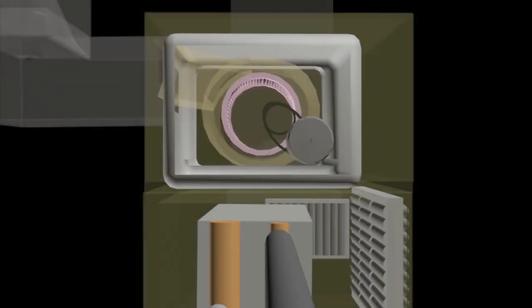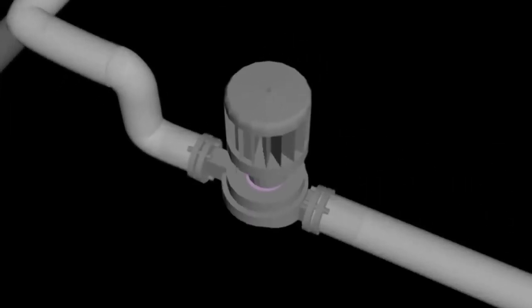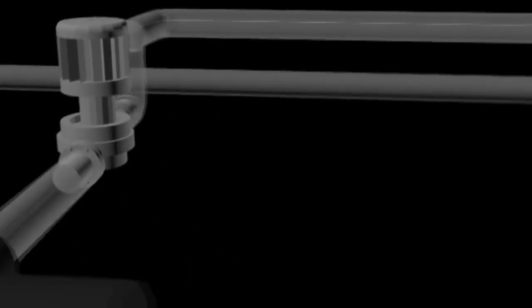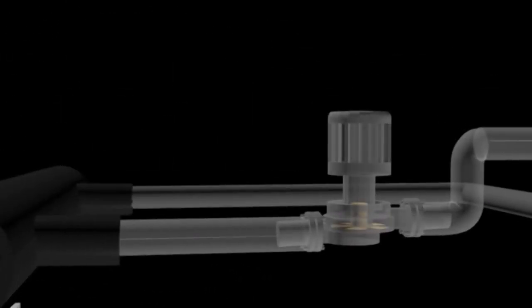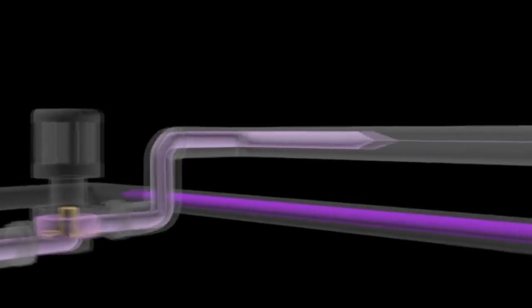The air handling unit is a place where cold air is produced before it can be distributed. It consists of several key components such as the cooling coil, fan motor, belting, filters and the casing. Chilled water produced in the evaporator will flow into the air handling unit through a pipeline which is marked with dark blue color. This chilled water is known as chilled water supply.